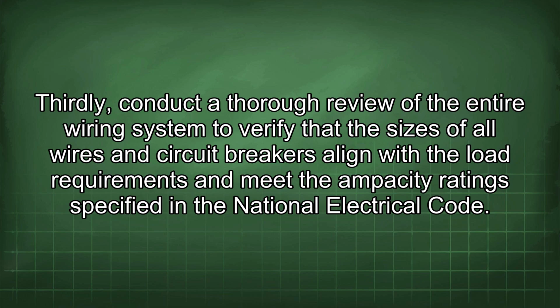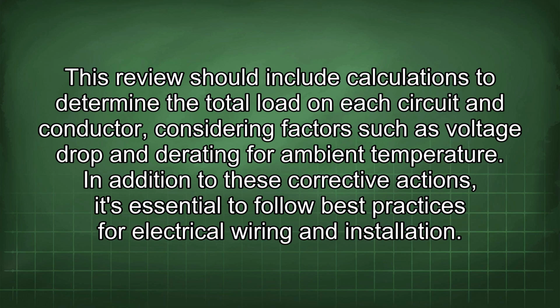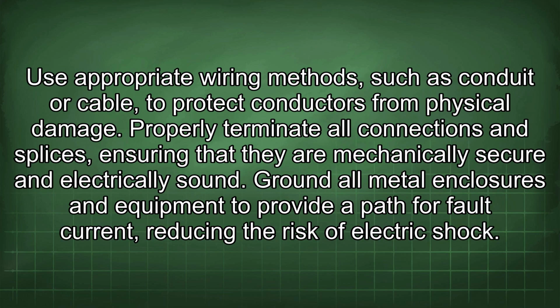Thirdly, conduct a thorough review of the entire wiring system to verify that the sizes of all wires and circuit breakers align with the load requirements and meet the ampacity ratings specified in the National Electrical Code. This review should include calculations to determine the total load on each circuit and conductor, considering factors such as voltage drop and derating for ambient temperature. In addition to these corrective actions, it's essential to follow best practices for electrical wiring and installation. Use appropriate wiring methods, such as conduit or cable, to protect conductors from physical damage. Properly terminate all connections and splices, ensuring that they are mechanically secure and electrically sound. Ground all metal enclosures and equipment to provide a path for fault current, reducing the risk of electric shock.